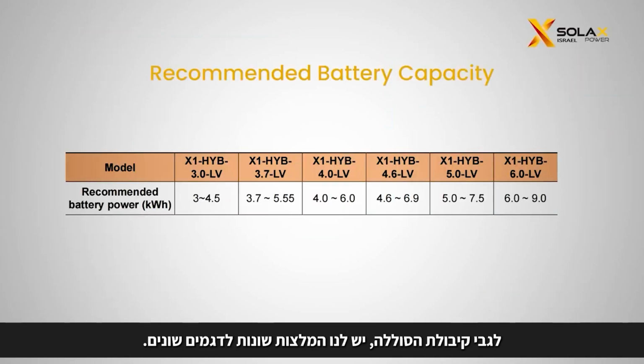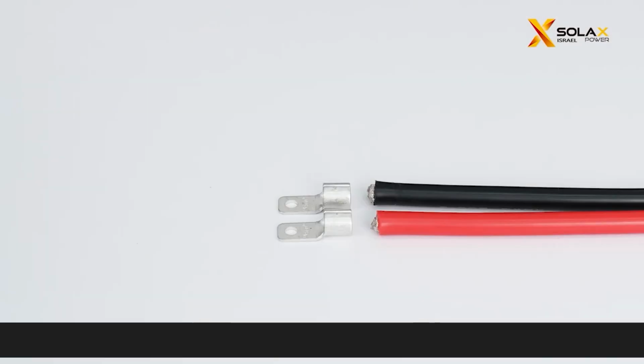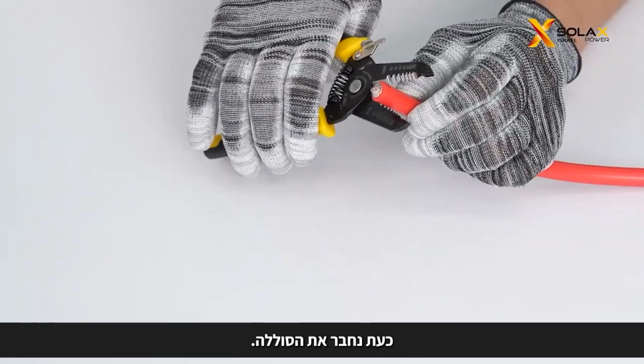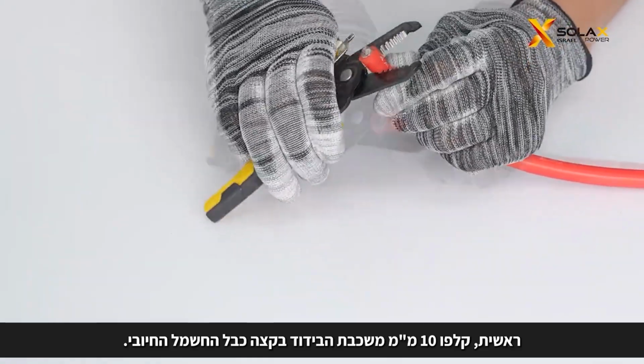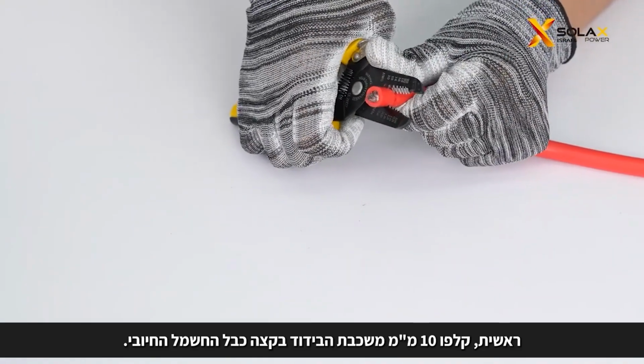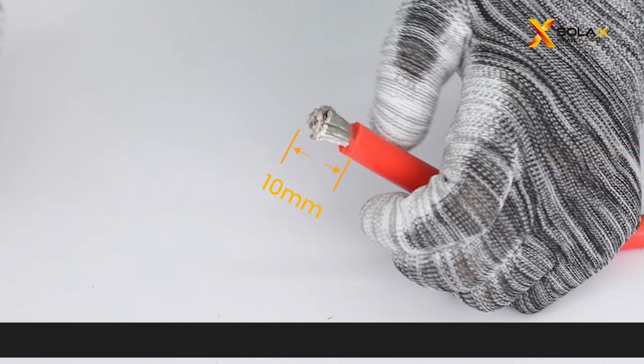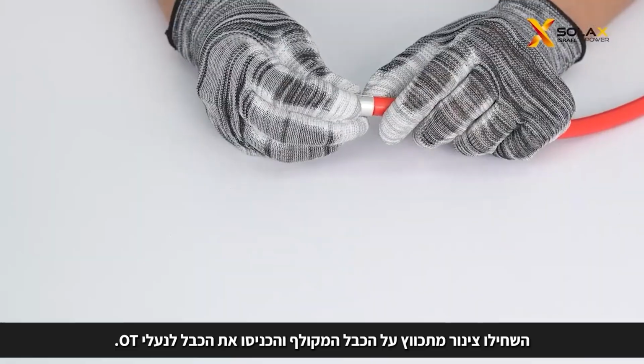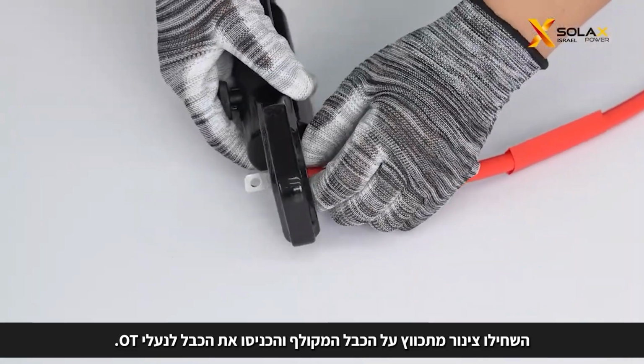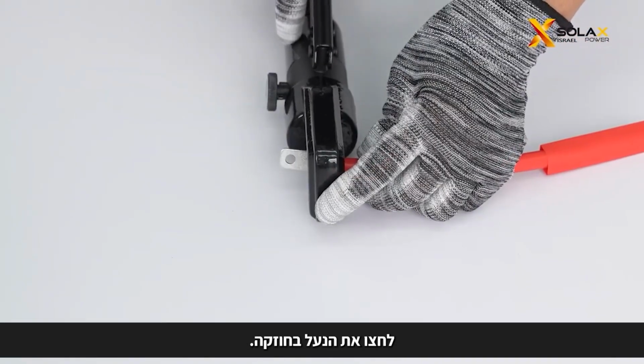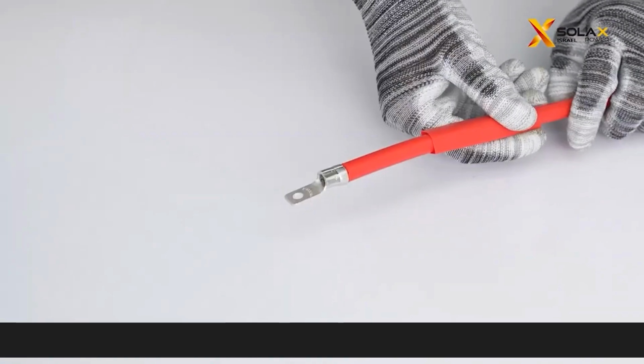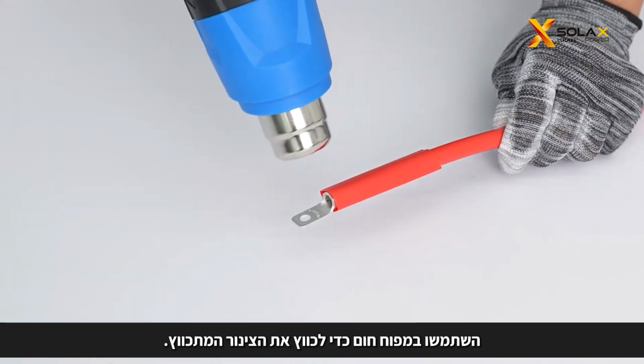For battery capacity, we have different recommendations for different models. Please refer to the table for the suitable battery capacity for each inverter model. Now let's connect the battery. Firstly, strip 10 mm of the insulation layer at one end of the positive power cable. Thread the heat shrink tube through the stripped cables and insert the cables into the OT terminals and crimp the terminal tightly. Use a heat gun to tighten the heat shrink tube.